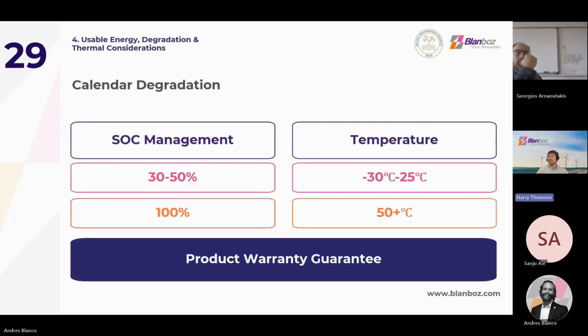So now we'll start looking at calendar degradation. This is degradation that occurs over time, regardless if the BESS is in use or not. This occurs at the beginning of the project typically, or if the equipment is stored. But there are ways to reduce and manage this. The 3 main factors that impact the rate are the duration of time, the state of charge during this time, and the temperature. The longer the equipment is stored or sat idle, the more degradation stacks up. The equipment is typically shipped from the factory at around 30 to 50% state of charge. This is the ideal range to minimize calendric degradation. If the state of charge is too high, or even 100%, then the cells have a larger electrochemical potential, are under larger stress, and this can increase calendar aging.